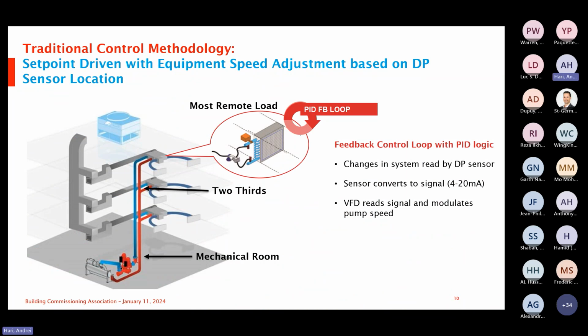traditional systems, typically there are three areas where the DP sensor will be located. I see a lot of installations where the differential pressure switch is located in the mechanical room across the supply and return of the pumps. ASHRAE is mandating that it's installed in the most remote load in the system. A lot of engineers will specify 2/3. So you're locating that DP sensor at the 2/3 point.